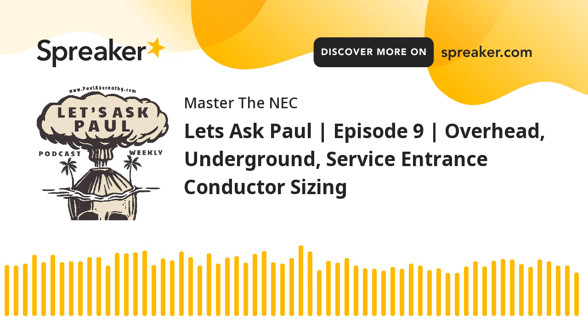So just remember that when you're doing your calculations. In the field, you're probably going to do the part 4 optional method most all the time. When it comes to the grounded neutral conductor, you're going to have to be sizing under part 3. So you're not going to totally get to ignore part 3, even if you're so heavily in part 4 for optional methods. Still got to know how to do it, right? And if you don't know how to do it, we have videos on that over on our YouTube channel. Just go to youtube.com/masterthenec. Go to the playlist called Calculations, and in there you will see videos on how to do service calculations for single family, multifamily. They're all there. Just go check them out.